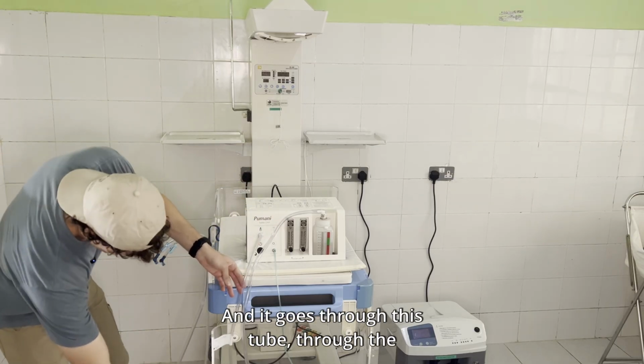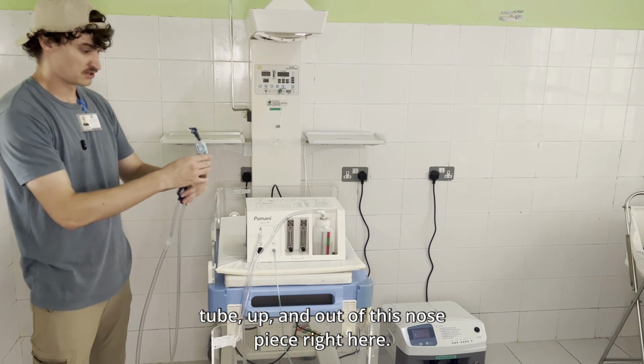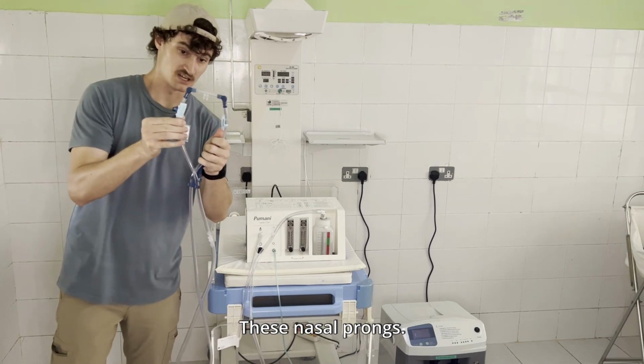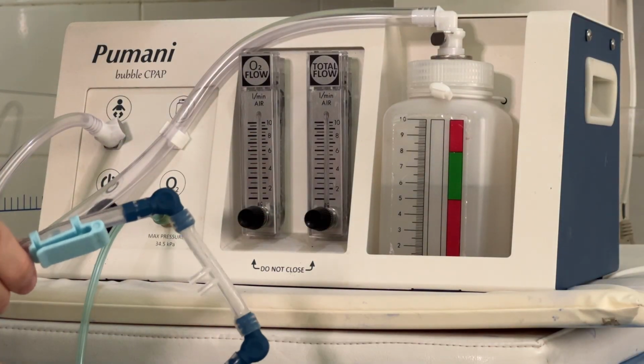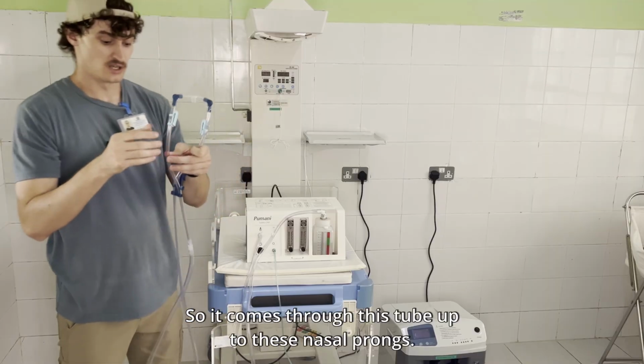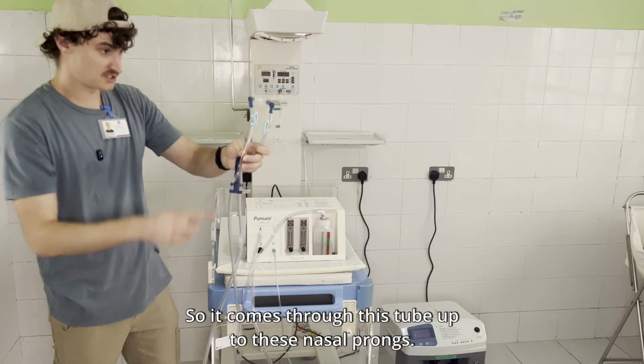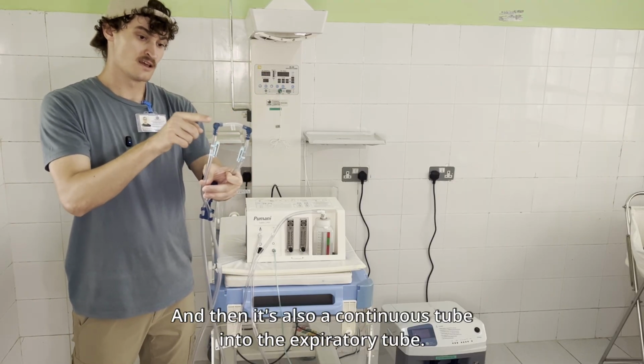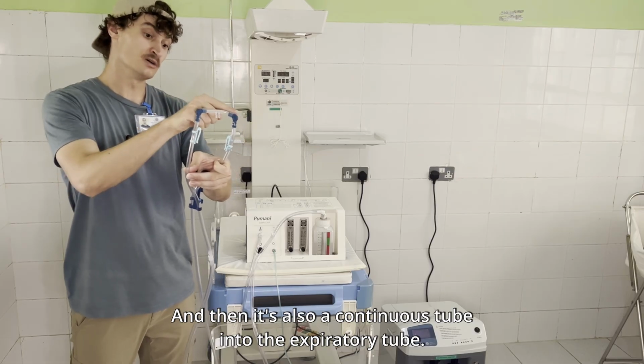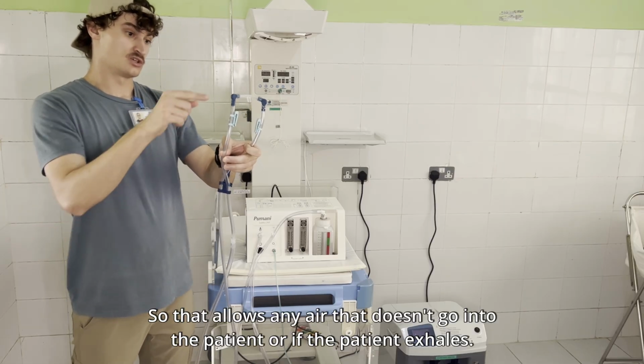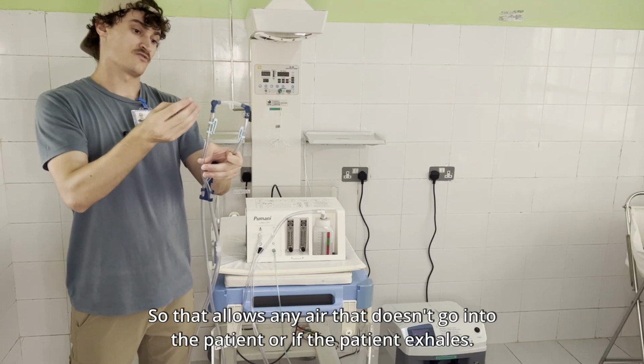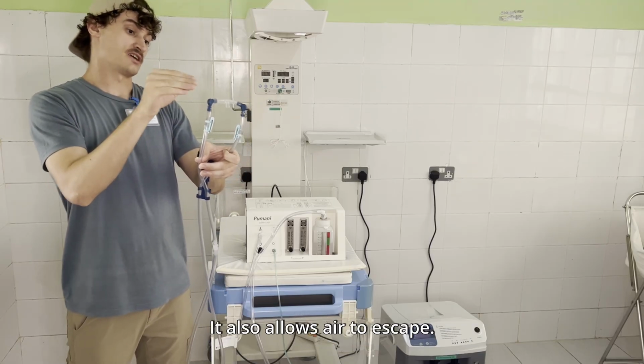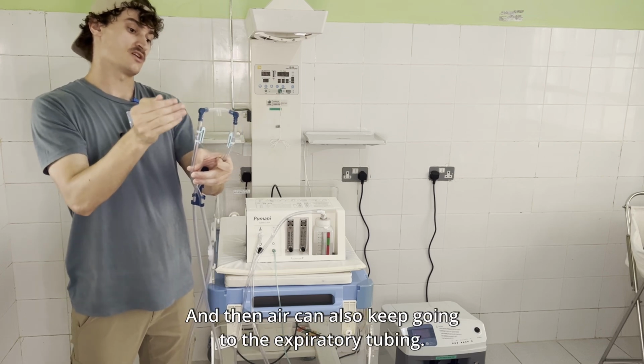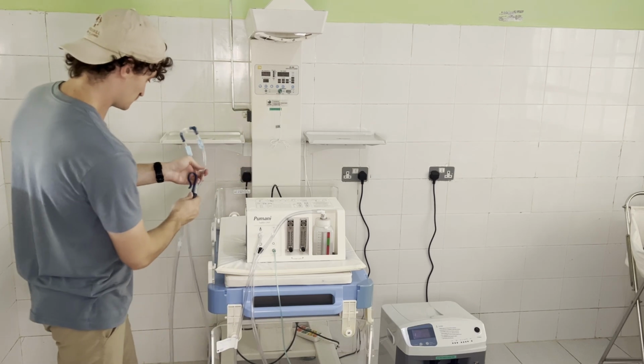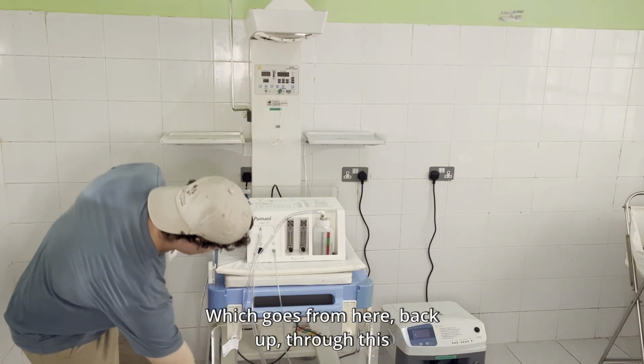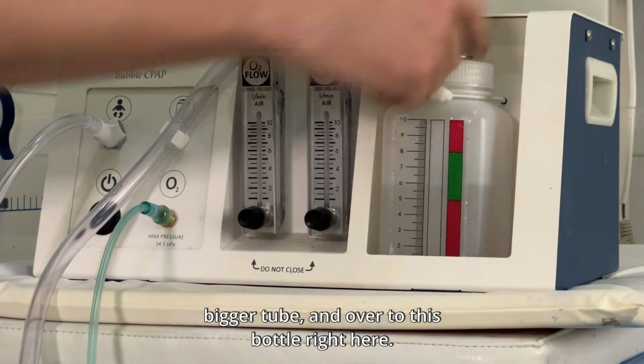And it goes through this tube, up and out of this nose piece right here. These nasal prongs, maybe I'll hold them down here so you guys can see better. These nasal prongs. So it comes through this tube up to these nasal prongs. It can go into the patient right there. And then it's also a continuous tube into the expiratory tube. So that allows any air that doesn't go into the patient, or if the patient exhales, it also allows air to escape. So it's providing constant pressure to the patient, and then air can also keep going to the expiratory tubing, which goes from here back up through this bigger tube and over to this bottle right here.